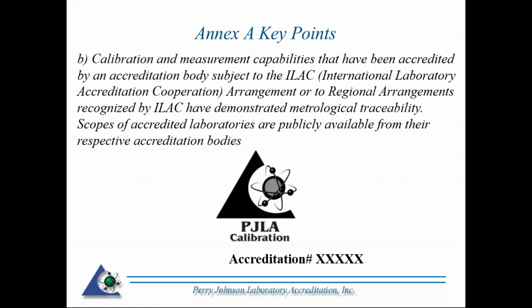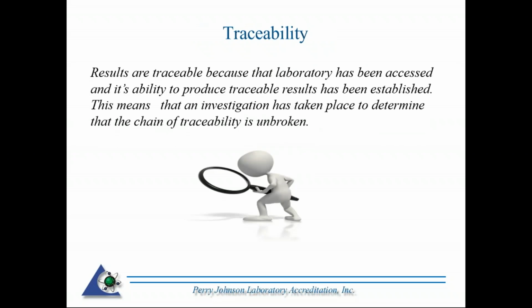So when you see that symbol on a report, that accreditation number is unique. With PJLA, that accreditation number is unique to that specific organization. So why do we state that they're already determined to be traceable? When you see that logo, you can look at it as a big stamp of approval. The results are traceable because the laboratory has been assessed and its ability to produce traceable results has been established. This means that an investigation has taken place to determine that the chain of traceability is unbroken. In other words, that is part of their assessment. In order to be accredited, the fact that they are producing traceable results has been assessed.